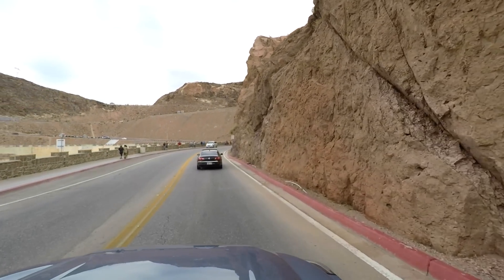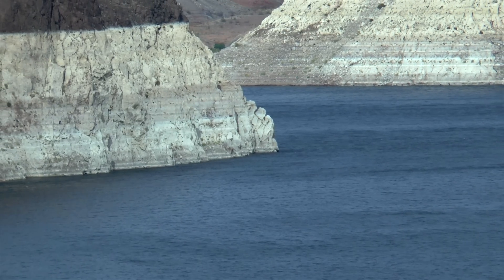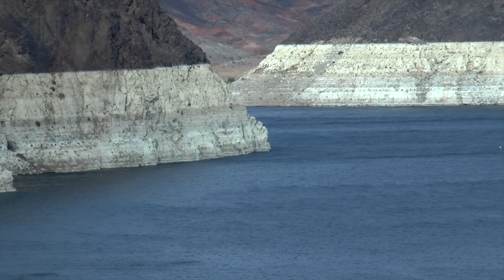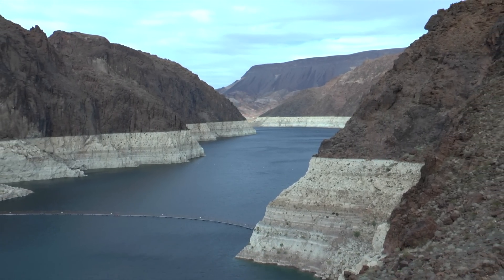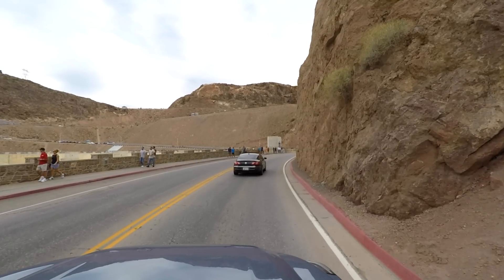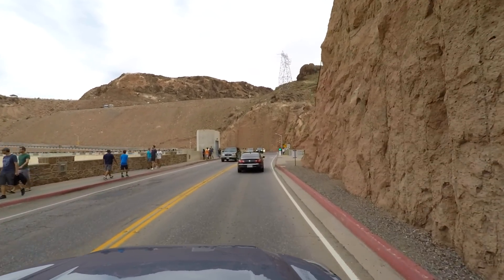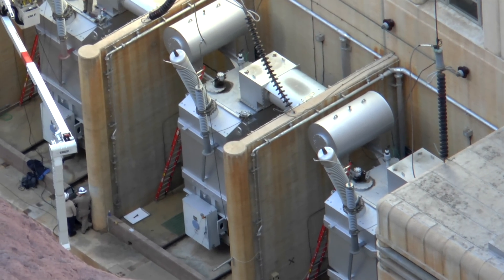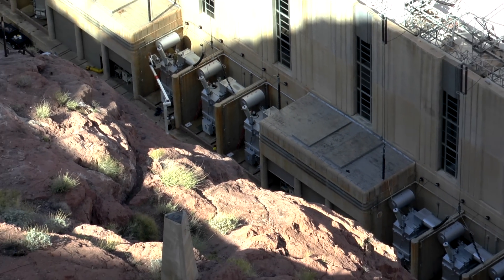So now that the turbines run more efficiently, the elevation of Lake Mead can now go all the way down to 950 feet and they are still able to produce electricity all the way down to that level. That's compared to the old configuration which kept the low level at about 1070 to 1050 feet, depending on where you read about it. And these two numbers are interesting when we take a look at what's going on right now with the water level.